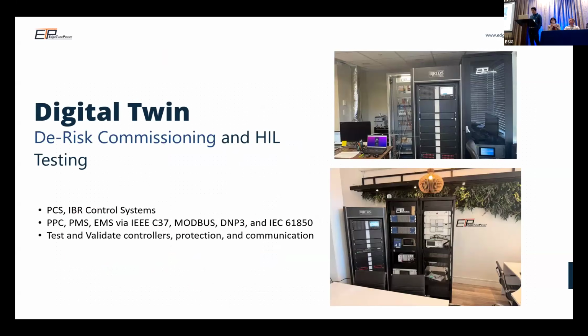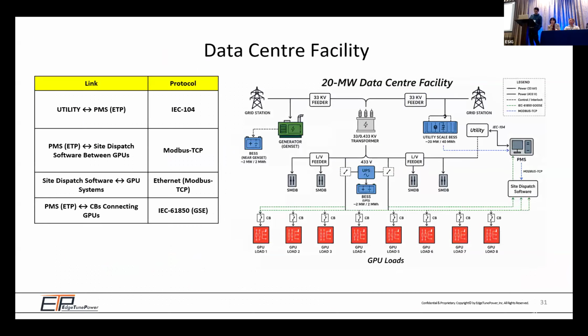And this is a picture of our real-time simulation laboratory. I'm going to pass this one. This is a model of the client that we worked with in Oman, and we are still working with them. It's a 20 megawatt data center facility. Between the utility and our power management system, we were even able to represent old communication protocols like IEC 104. The utility said this is the communication protocol that I want to go with, and you have to represent it. We were able to successfully represent that in our test bed.